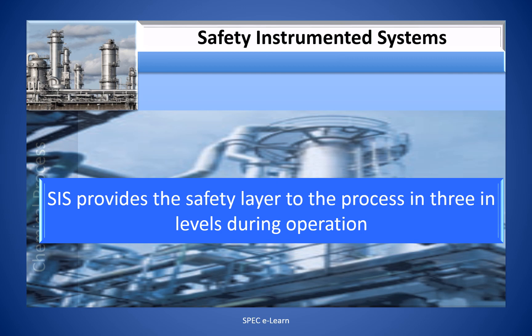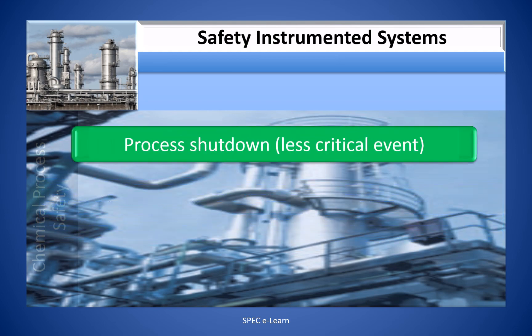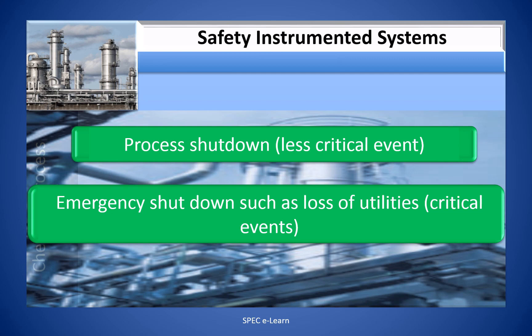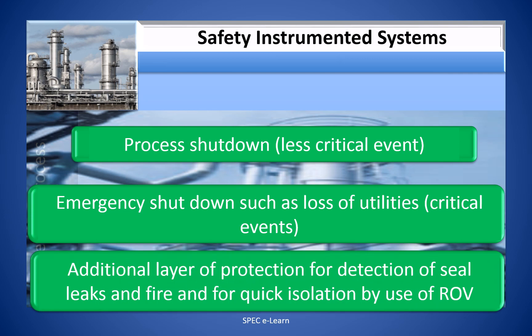SIS provides safety layers to the process in three levels during operation. One: process shut-down for less critical events. Two: emergency shut-down such as loss of utilities for critical events. Three: an additional layer of protection for detection of gas leaks and fire, and for quick isolation by use of ROVs.